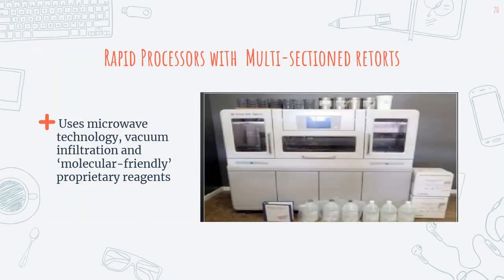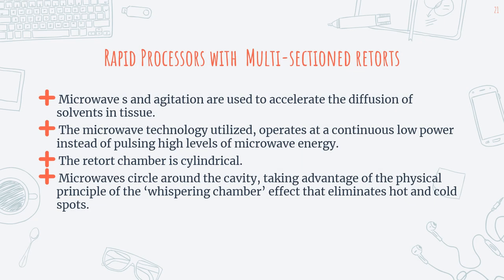For rapid processors with multi-section retorts, microwave technology, vacuum infiltration, and molecular-friendly proprietary reagents are used. Microwaves and agitation are used to accelerate the diffusion of solvents in tissue. The microwave technology operates at a continuous low power instead of pulsing high levels of microwave energy. The retort chamber is cylindrical and the microwave circles around the cavity, taking advantage of the physical principle of the whispering chamber effect that eliminates hot and cold spots.